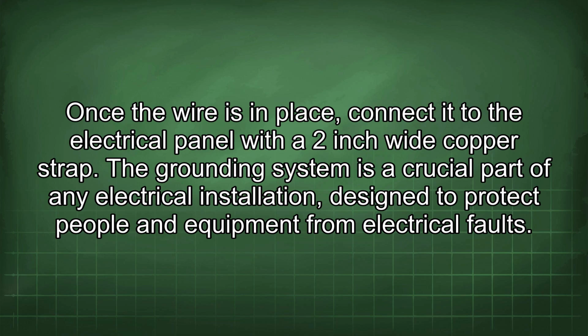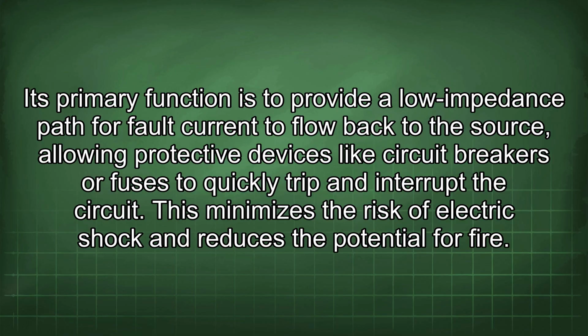The grounding system is a crucial part of any electrical installation, designed to protect people and equipment from electrical faults. Its primary function is to provide a low impedance path for fault current to flow back to the source, allowing protective devices like circuit breakers or fuses to quickly trip and interrupt the circuits. This minimizes the risk of electric shock and reduces the potential for fire.